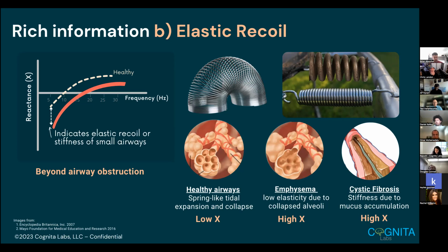Yes, you're very right to point that out, because anything that becomes more sensitive usually has higher variability. That's where the challenge happens. ERS has specific guidelines on what the variability of the measurement should be for a good test. For oscillometry measurements, the guideline is under 10% for adults and under 15% for children. So if you've done 3 measurements, the variability between them should be within 10% for adults, and for children, less than 15%.